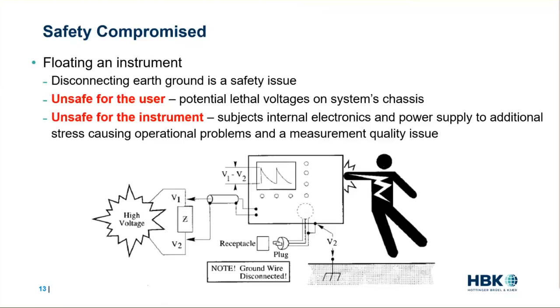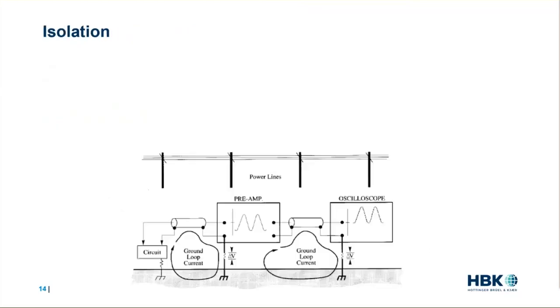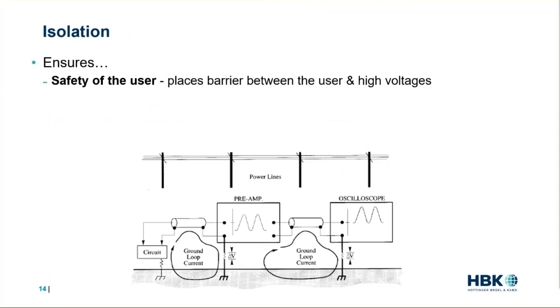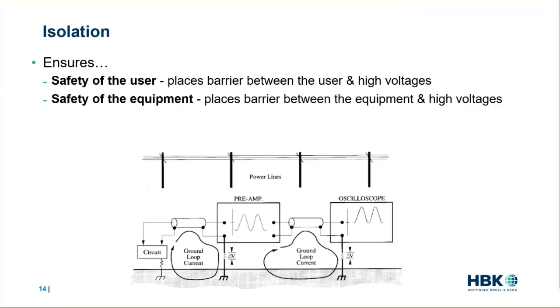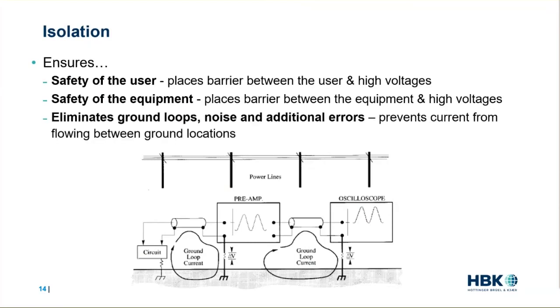So, what is the solution? Well, the solution is to use isolation. This is going to ensure the safety of you, the user. It places a barrier between the user and the high voltages, and also provides safety for the equipment, placing a barrier between the equipment and the high voltages. Now, please note that the barrier is only limited to the amount of isolation stated in the equipment specification. Also, it eliminates ground loops, noise, and additional errors by preventing current from flowing between ground locations. We'll talk more about isolation in each of the different power applications in a moment.